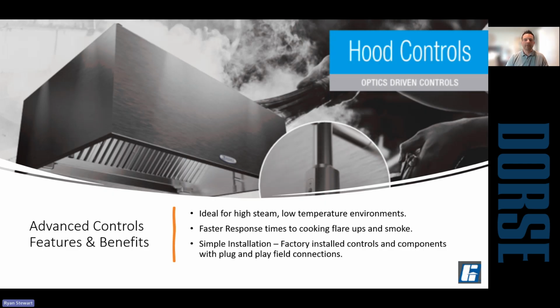The next step in demand control is adding an optic sensor. This is something that has been available from various manufacturers over the years. Greenheck has just added this to their line. What it does is give the system the ability to look at smoke. It sends a beam from one side of the hood to the other. It just gives a faster response when you have flare-ups or when you throw product onto a cooking surface.